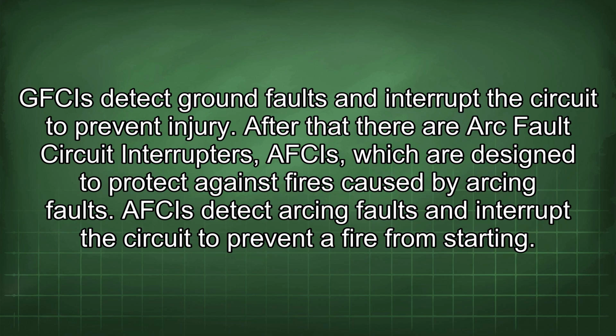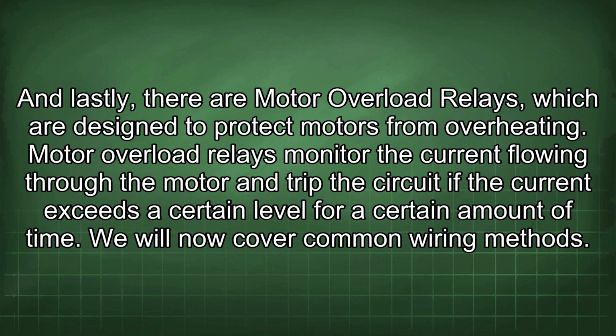After that, there are arc fault circuit interrupters, or AFCIs, which are designed to protect against fires caused by arcing faults. An AFCI detects arcing faults and interrupts the circuit to prevent a fire from starting. And lastly, there are motor overload relays, which are designed to protect motors from overheating. Motor overload relays monitor the current flowing through the motor and trip the circuit if the current exceeds a certain level for a certain amount of time.